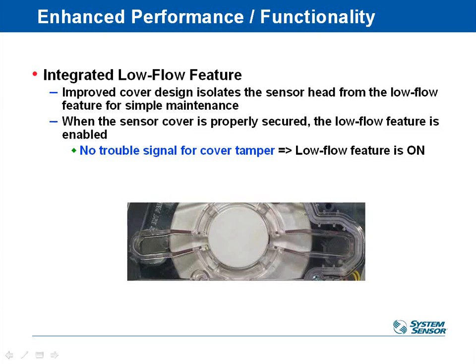Like I said, these guys can handle pretty low flow, and the way they do that, this is the detector head itself. On the left side is the supply air sampling tube connection. On the right side is that exhaust connection going back into the duct. So it draws air through the supply, across the head of the detector, and then back into the return duct. And you can see the plastic has been formed here to shrink down, to reduce, which will increase our velocity.